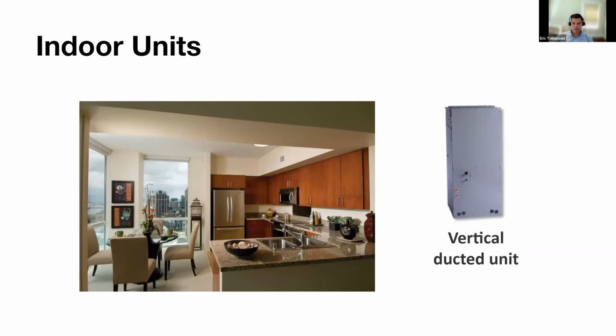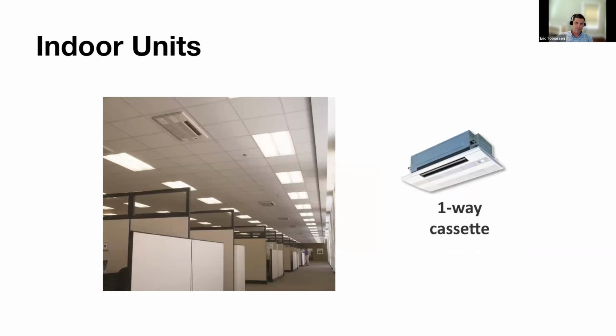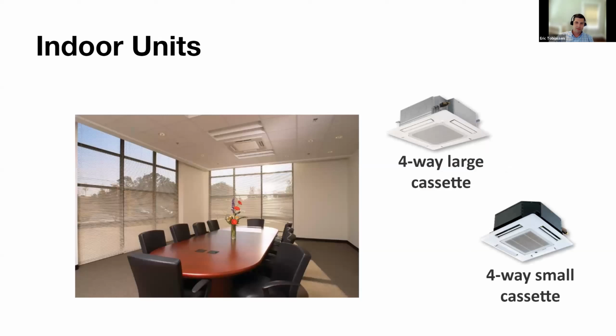And then there's the vertical multi-position ducted unit as well. These are popular. And again, you're just bringing refrigerant piping to this unit and then serving your spaces from ductwork. Then there's two different styles of cassettes. There's the one-way cassette. These go up in the ceiling. And then there's four-way cassettes. There's larger and smaller four-way cassettes. And this is really good. You put this in the middle of the room, and then you can get all four corners of your room with conditioned air.